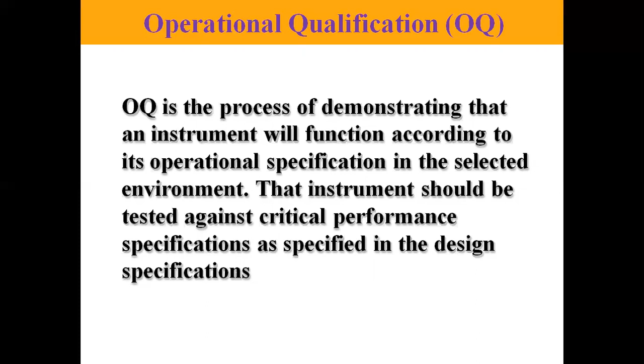The next one is OQ, operational qualification. OQ is the process of demonstrating that an instrument or equipment will function according to its operational specification in the selected environment. That instrument or equipment should be tested against critical performance specifications as specified in the design specification. Finally, this is performance qualification.